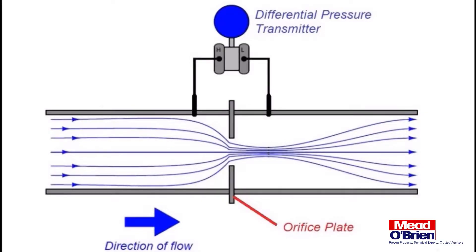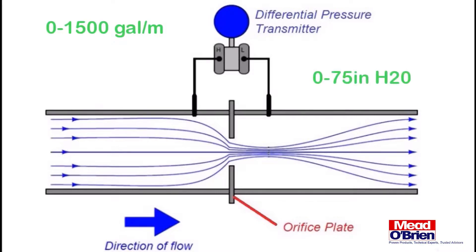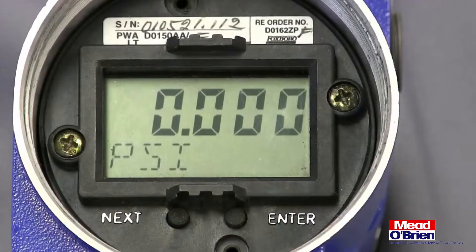Prior to configuring the transmitter, it is necessary to know the maximum flow rate you wish to measure and the differential pressure across the primary element at that flow rate. For demonstration purposes, we are going to configure our transmitter for a range of 0 to 1,500 gallons per minute at a differential pressure of 0 to 75 inches of water.